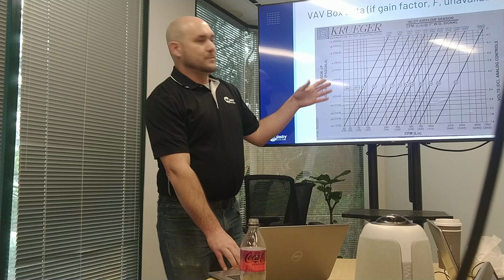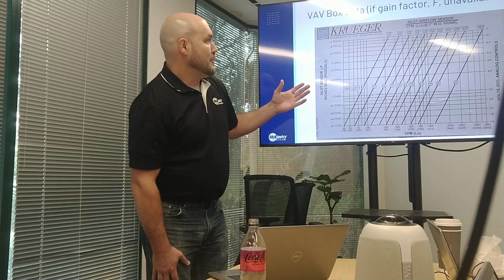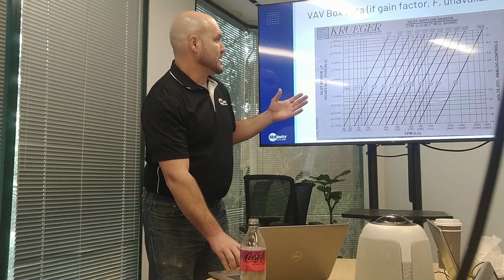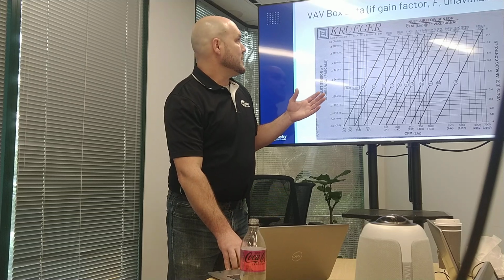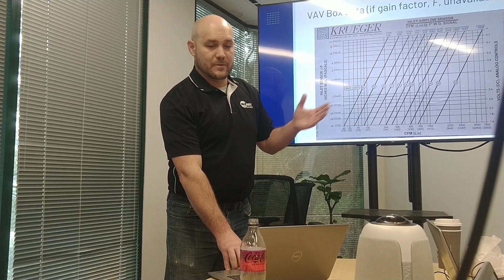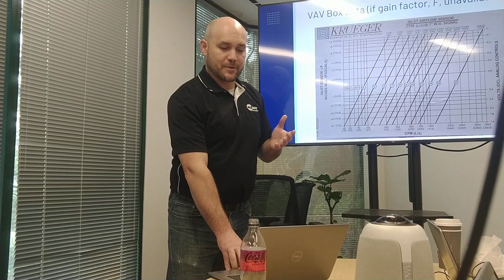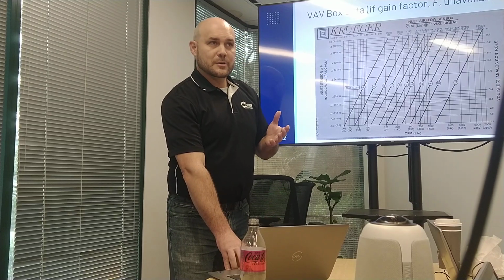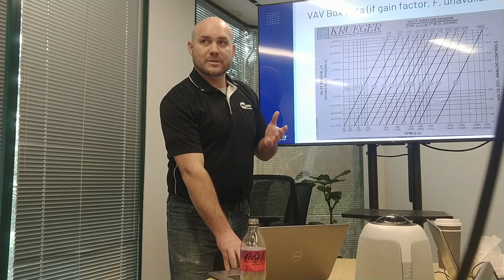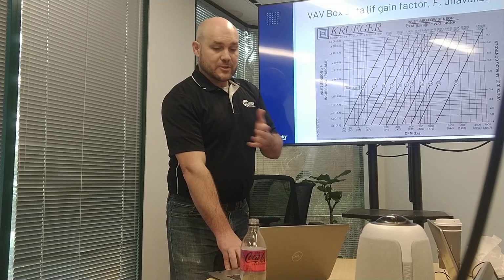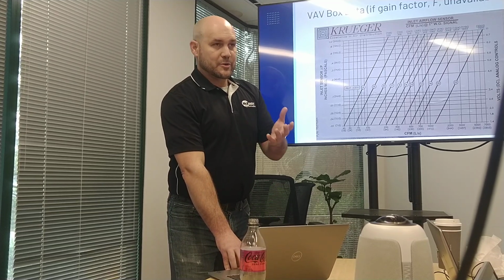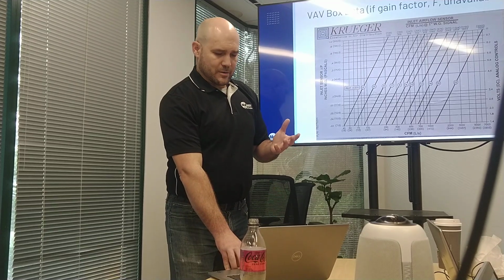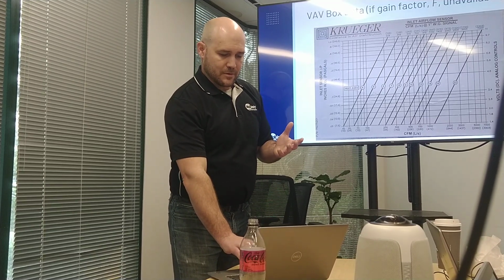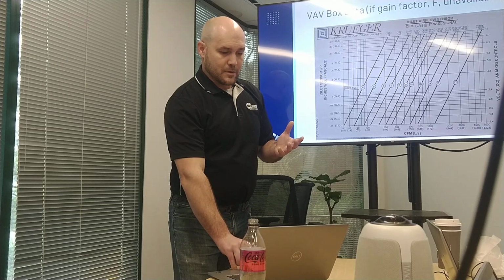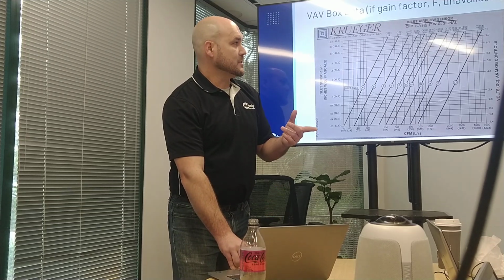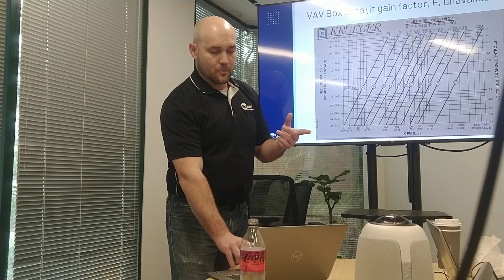So here's a picture from the side of a VAV box, and we're trying to see, well, what is the gain factor. Anybody remember what the gain factor was a function of in terms of what minimum values? Yeah, so we're trying to calculate the minimum controllable airflow for the box. But do you remember what that was a function of? Area over CFM squared, right? Or area times that factor. So yeah, the CFM at 1 inch pressure drop.